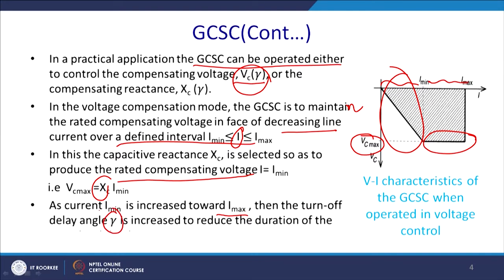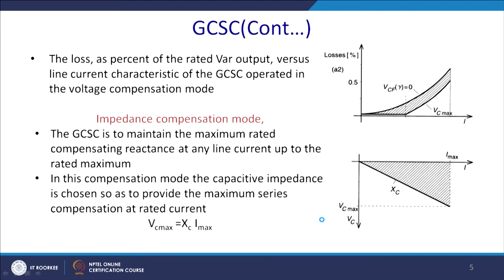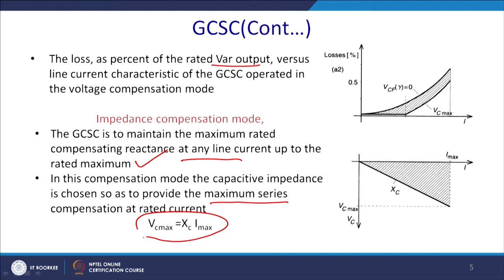Here the voltage remains constant in one region, and the slope remains constant (constant impedance) in the other. As the current I_min increases towards I_max, the turn-off delay angle gamma is increased to reduce the duration of conduction. The loss as a percentage of rated VAR output versus current characteristics of the GCSC operated in voltage compensation mode is shown here.